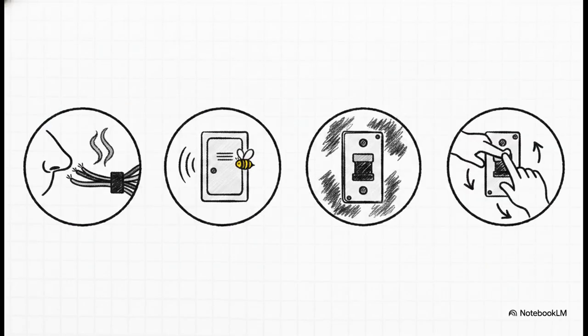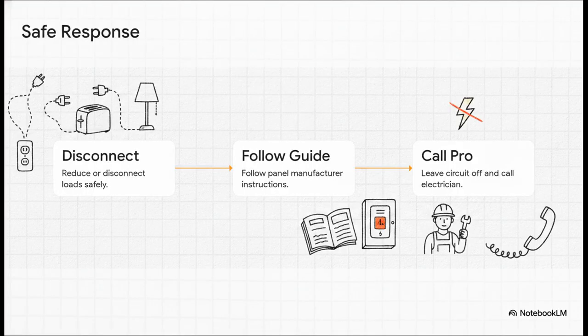You also really need to watch out for these danger signs. If your electrical panel smells hot, if you hear buzzing sounds, if you see discoloration, or if the breaker simply will not reset, the trip isn't just a summer nuisance anymore. It's a severe warning. It could be an overloaded circuit, a failing motor, or a highly dangerous wiring fault. To properly investigate this, follow these exact steps for a safe response.